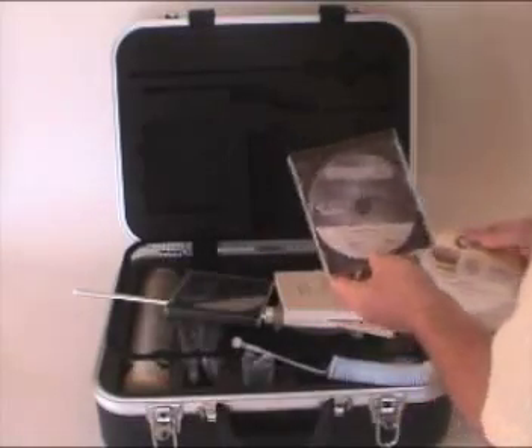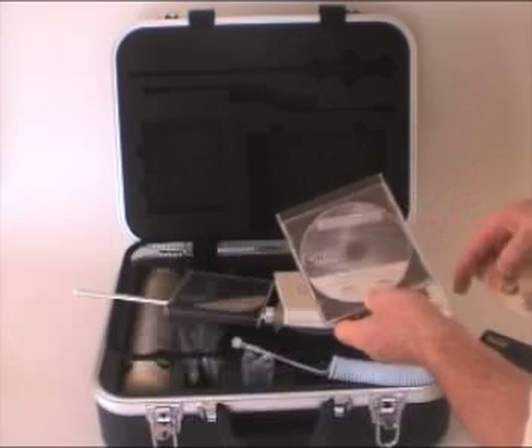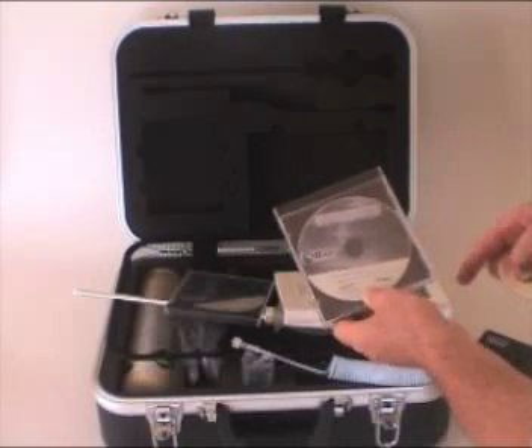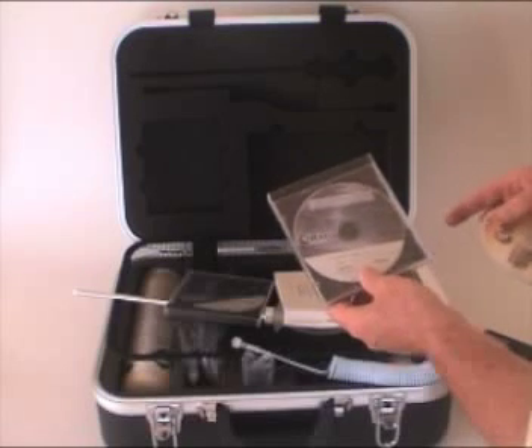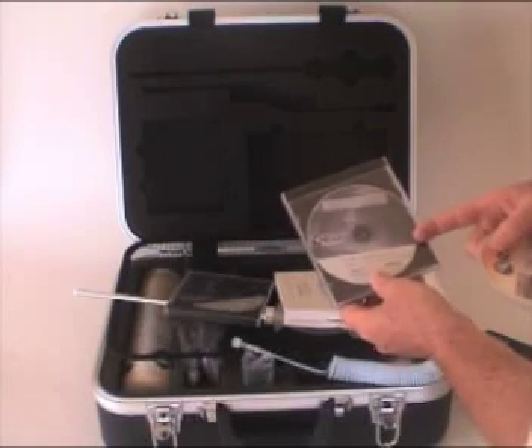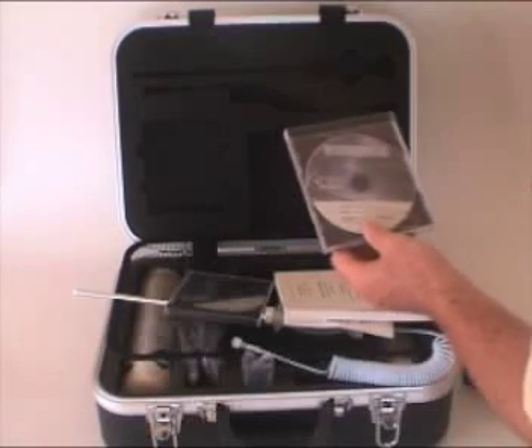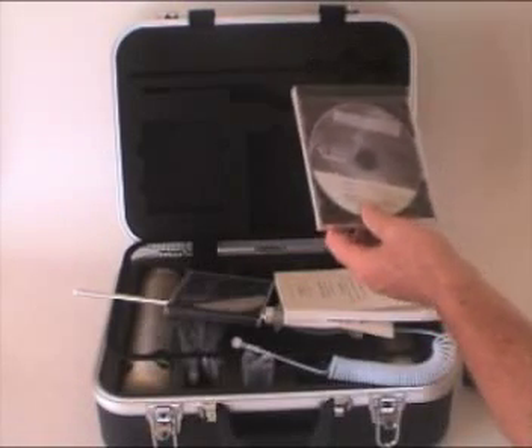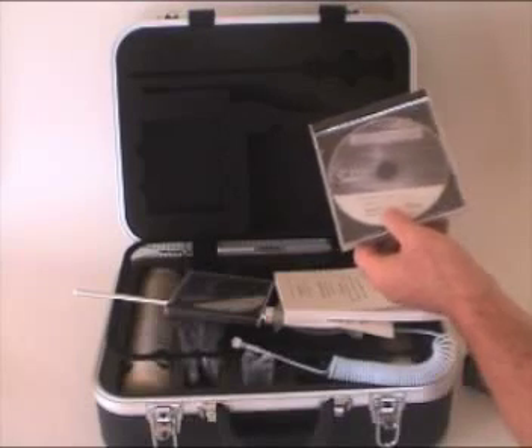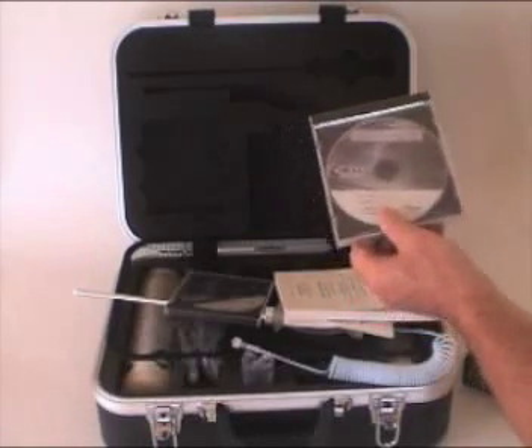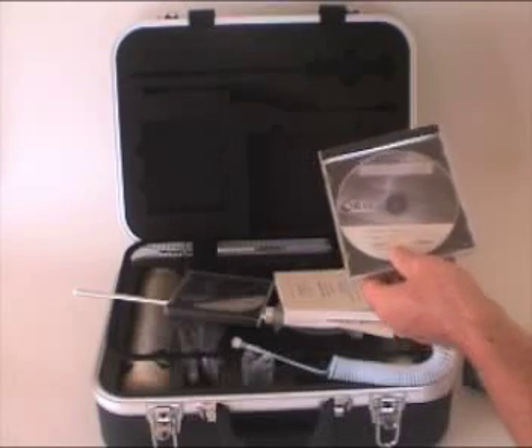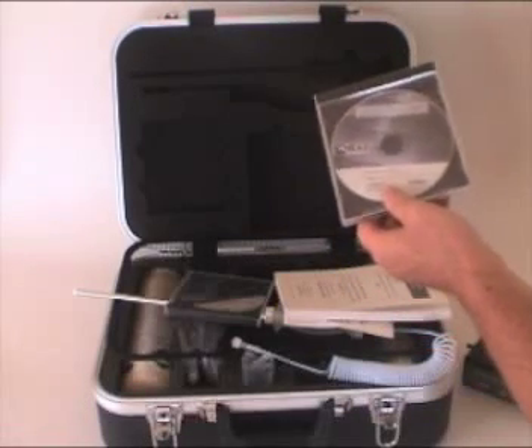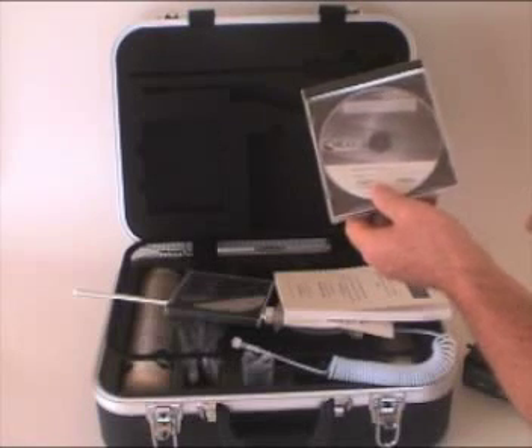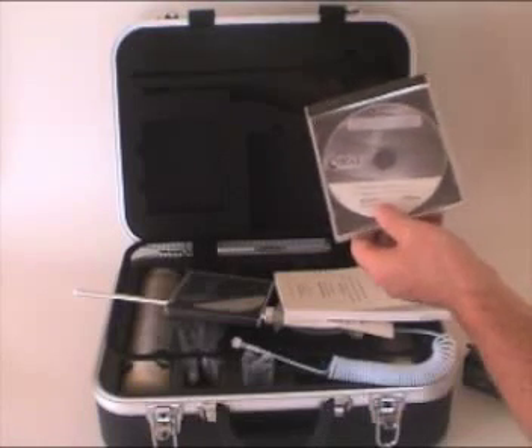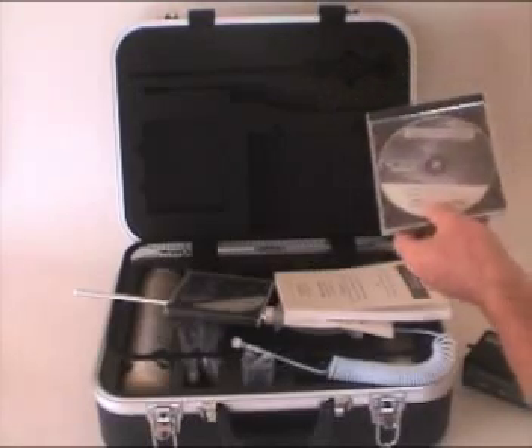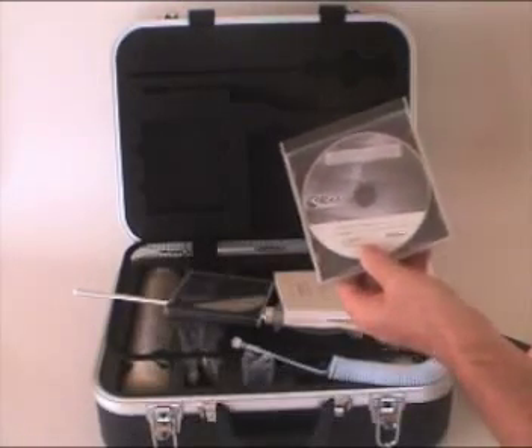This is our data logging software for the unit. It does event recording within the unit, and there's quite a few things you can do with it. The idea is to connect the unit to your Windows-based machine and download everything it's recorded. You might put together an Excel spreadsheet of highs and lows. It also has a graphing function showing concentration levels of all 5 sensors over time, which is useful for seeing what your workers are exposed to, and whether they're using the unit properly.